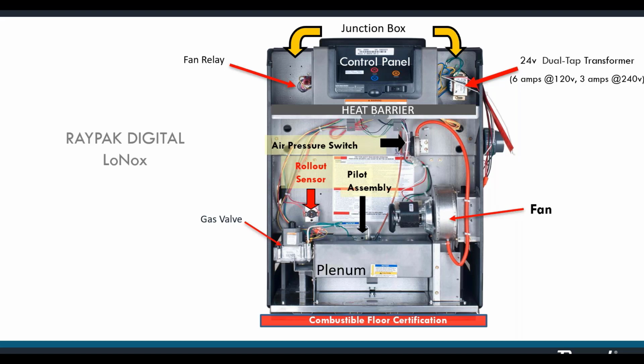At the same time, the gas valve will open and release gas into a manifold that is located inside that plenum. From there, those 2 elements of fuel are pushed into the burners where they mix and come out the top to ignite. Down at the bottom, you'll notice there is a flame viewport. This particular model has a bit of a bulkhead there that seals off the flame from view. We've had to put a flame viewport there so that you can make sure, if necessary, if the pilot is lit properly. And of course, our bonding lug attaches here on the lower right-hand corner of the cabinet.